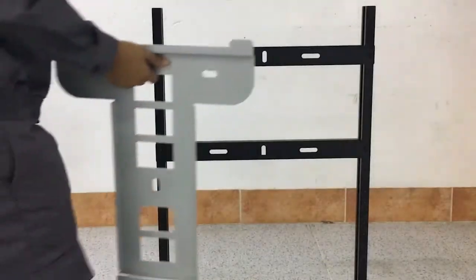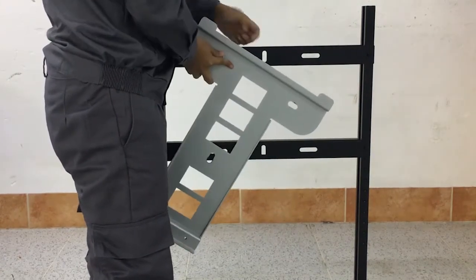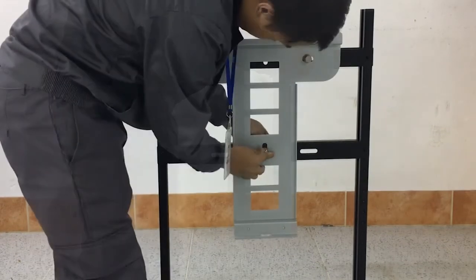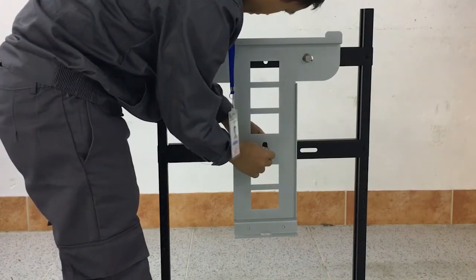Check whether the rear panel can be mated with the support. If not, locate appropriate drilling holes and mark them with a 2B pencil. Drill the holes. Tighten the rear panel on the support using the adjustable wrench to a torque of 45 Nm.